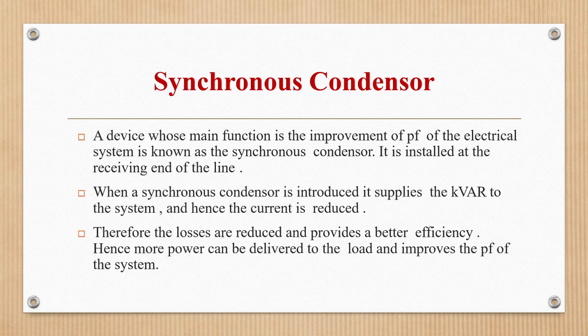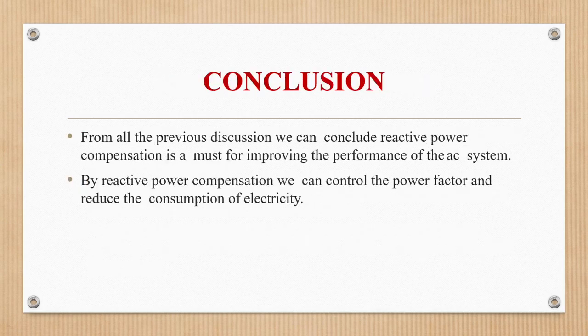A synchronous condenser is a device whose main function is the improvement of the power factor of an electrical system. It is installed at the receiving end of the line. When a synchronous condenser is introduced, it supplies kVAR to the system, thereby reducing the current. As a result, losses are reduced and efficiency improves. More power can be delivered to the load and the power factor of the system is improved. Reactive power compensation is essential for improving the performance of the AC system, controlling power factor, and reducing electricity consumption.